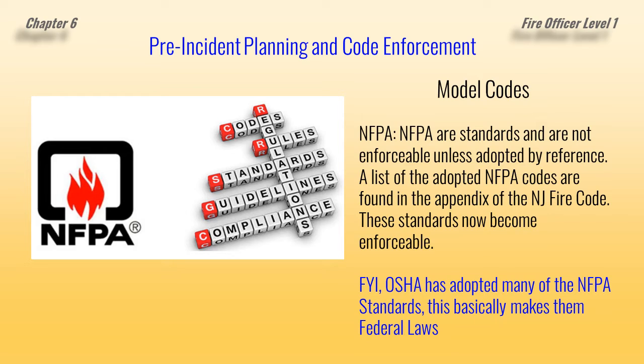So if we take the International Building Code, it is going to reference NFPA 13 for sprinklers. So it's basically adopted. Once it becomes adopted, it becomes a law that you have to follow. Same thing in OSHA. Now, anything in OSHA is considered a law because it's a federal standard. Once you put federal regulations in there, that makes it a federal law.